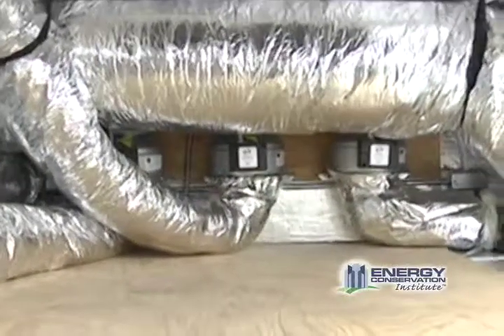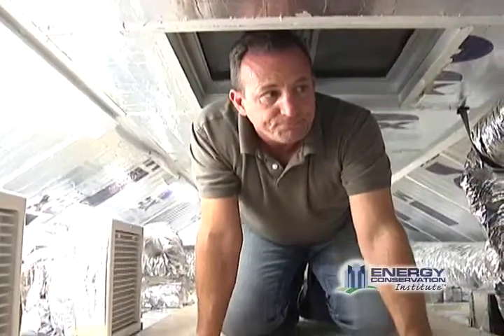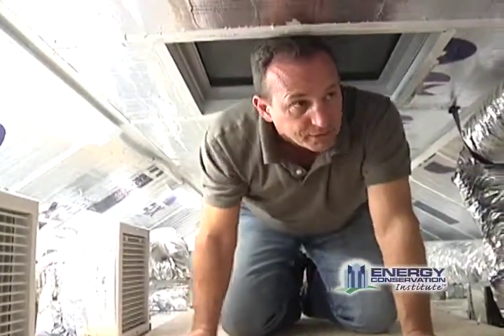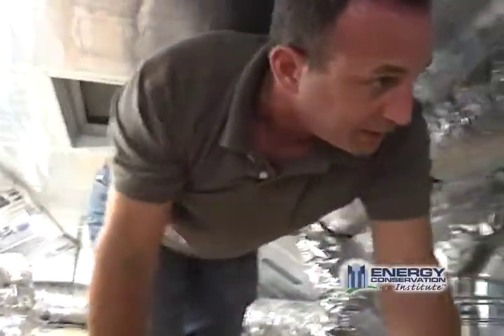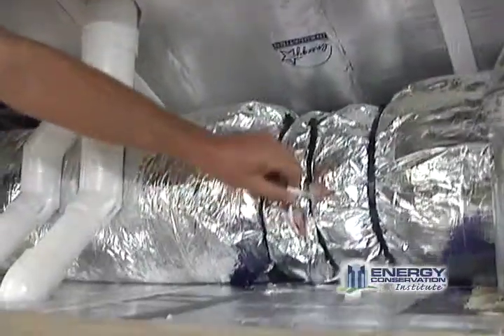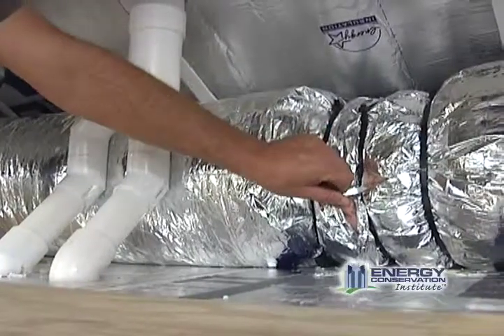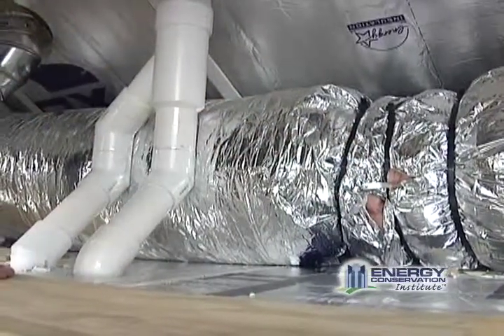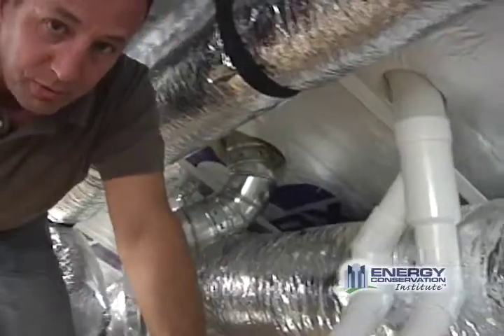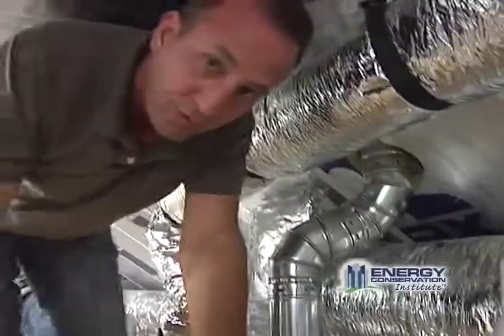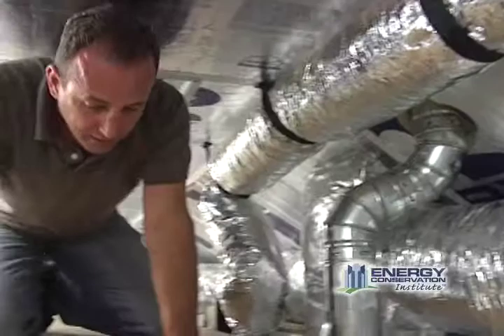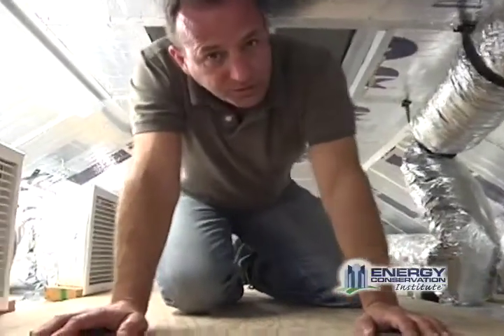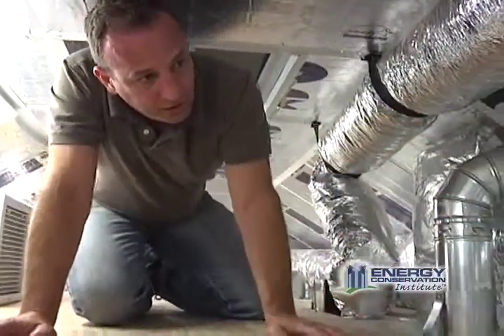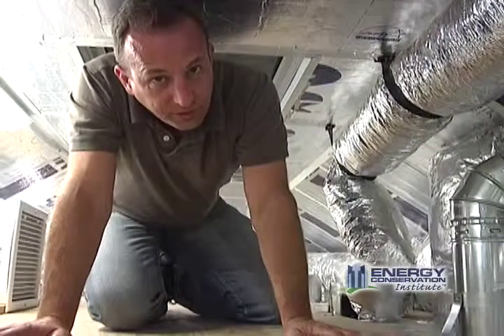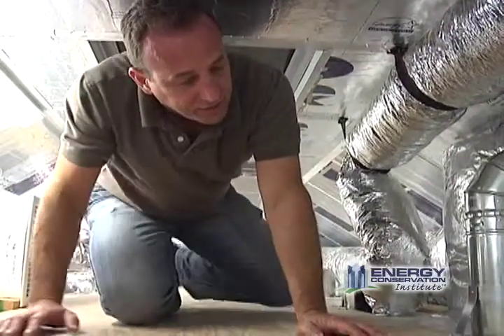Although we've insulated everything here, there are a couple of deficiencies worth pointing out. One other thing in the ductwork here is a damper—an adjustable damper—so you can do static pressure testing and control your static pressure. As mentioned earlier, in that 80% unit we have holes drilled in the box itself so you can measure static pressures, and by opening and closing that damper you can greatly impact the static pressures.